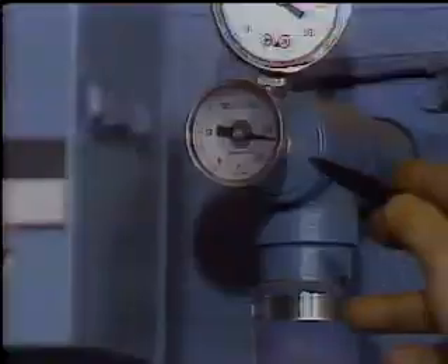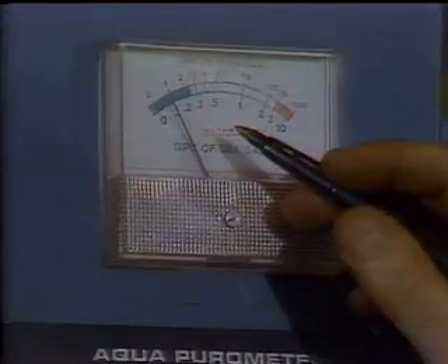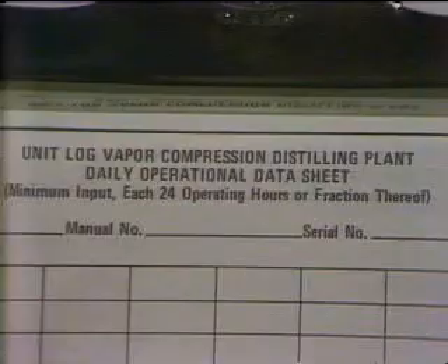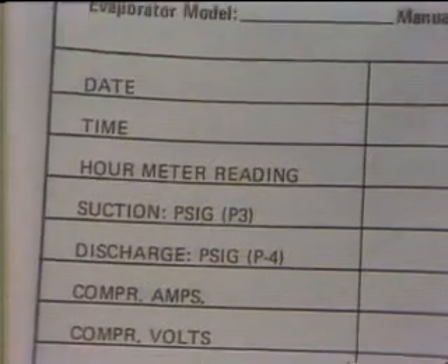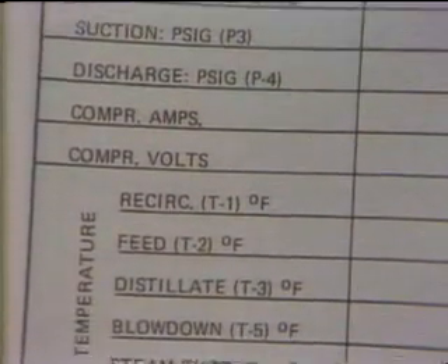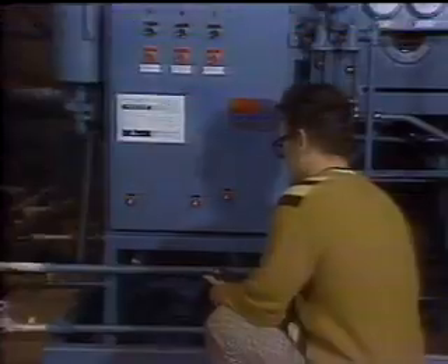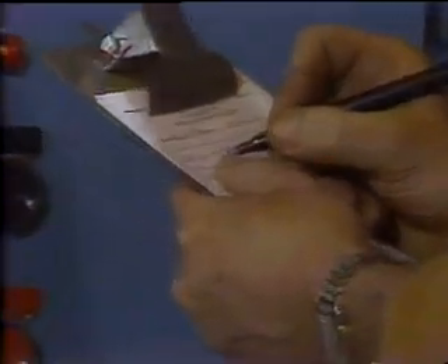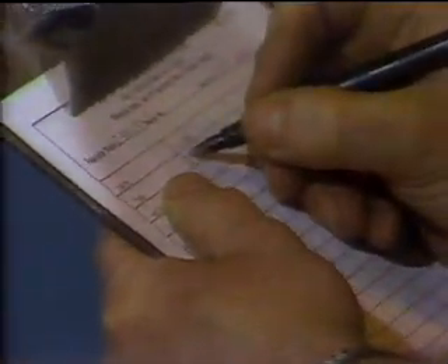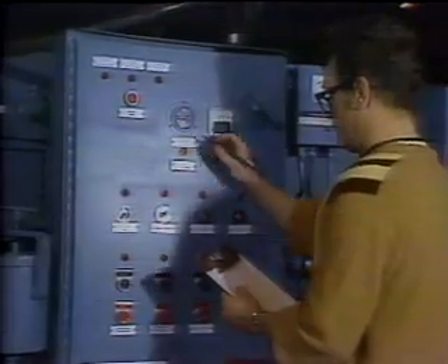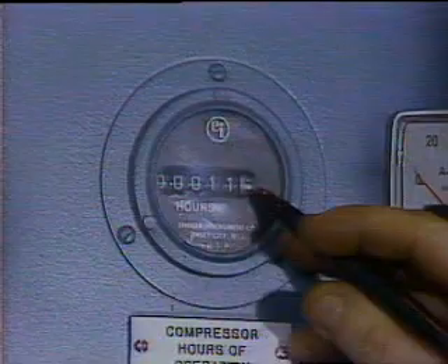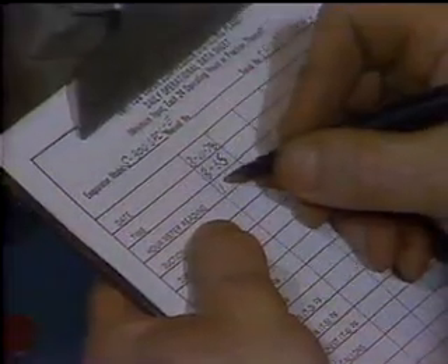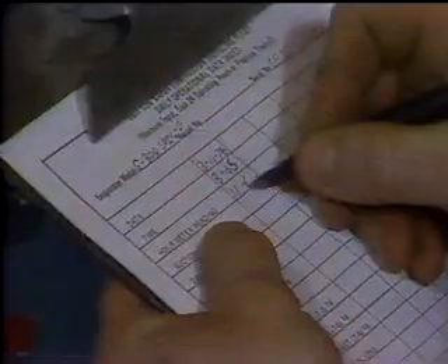Remember, you should take these readings every day, and you'll have to do it while the water maker is operating. The form that is to be filled out is the daily operational data sheet. All of the different gauges on the Aquachem are listed here. First, you'll need the model and serial numbers off of the nameplate on the control panel. Then the date and time of day should be filled in. Next, the total number of hours that the system is operated, off of this hour meter. This will help you in determining how many hours the system has been run.